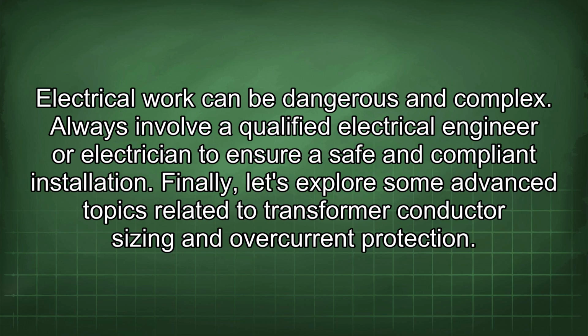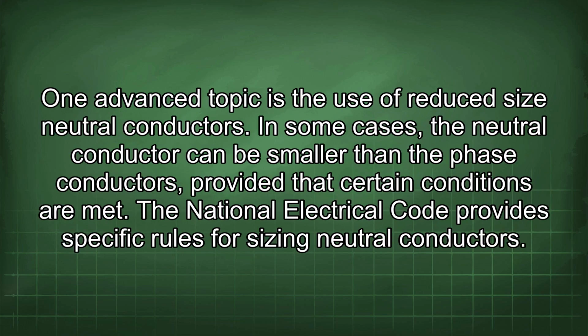Finally, let's explore some advanced topics related to transformer conductor sizing and overcurrent protection. One advanced topic is the use of reduced-size neutral conductors. In some cases, the neutral conductor can be smaller than the phase conductors, provided that certain conditions are met. The National Electrical Code provides specific rules for sizing neutral conductors.